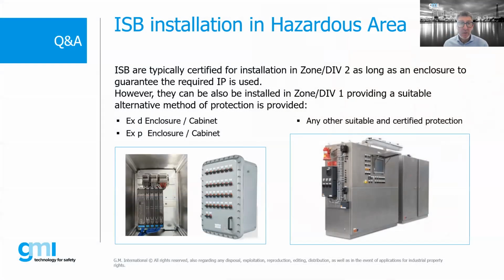Can I install an IS barrier in a hazardous location? If you take for example, they are certified for installation in zone 2. But if you want to go in zone 1 or zone 0, you cannot, unless you install them properly. That's where we saw that box earlier where we saw an EXD box marked EXD, and then in brackets should have IA. That means we had a flameproof box with associated apparatus providing protection downstream. So absolutely, you can install barriers in hazardous locations, but be aware of the limitations based upon the selection and based upon the barrier, where you can and cannot install them.